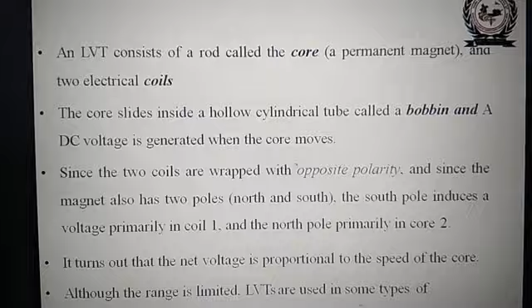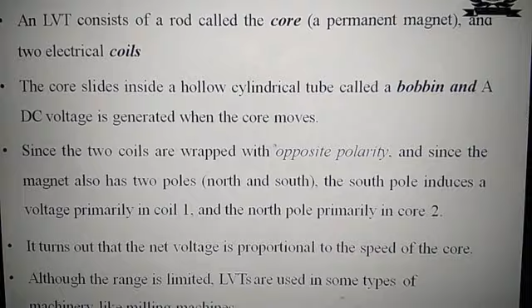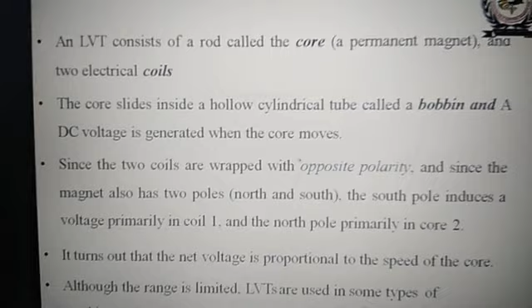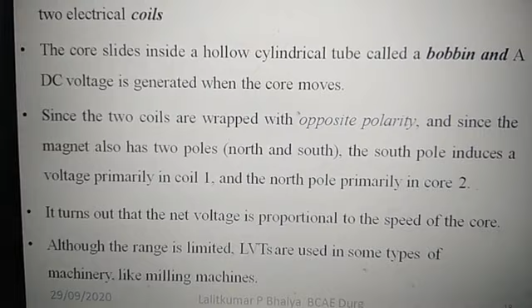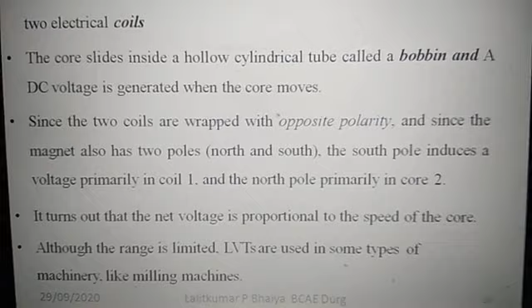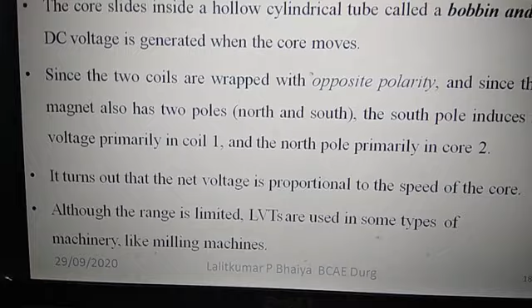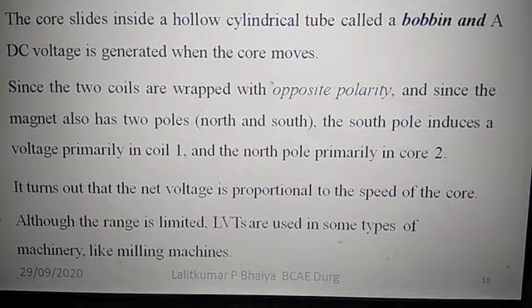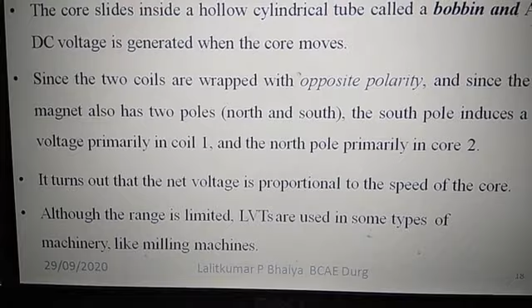An LVT consists of a rod called the core, a permanent magnet, and two electrical coils. The core slides inside a hollow cylindrical tube called the bobbin, and a DC voltage is generated when the core moves. Since the two coils are wrapped with opposite polarity, and since the magnet also has two poles, north and south, the south pole induces a voltage primarily in coil 1 and the north pole primarily in coil 2. It turns out that the net voltage is proportional to the speed of the core. Although the range is limited, LVTs are used in some types of machinery like milling machines.